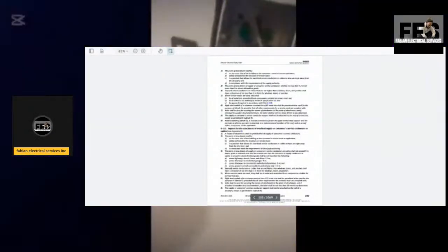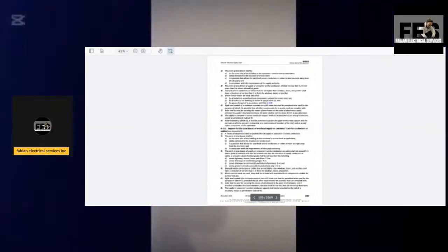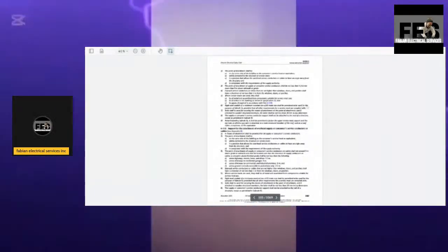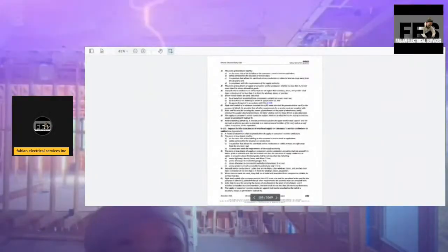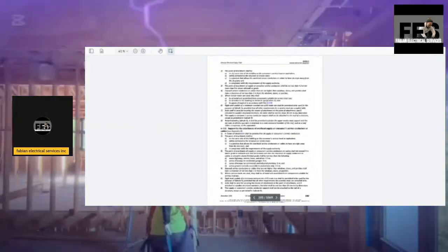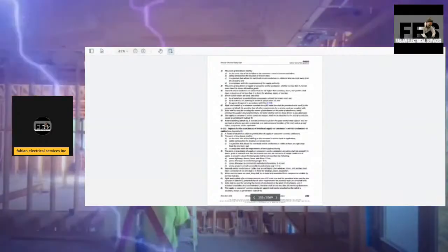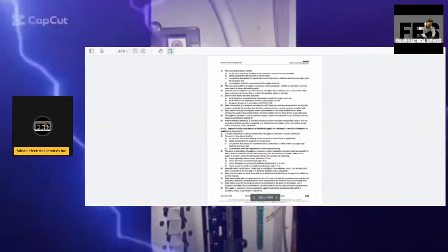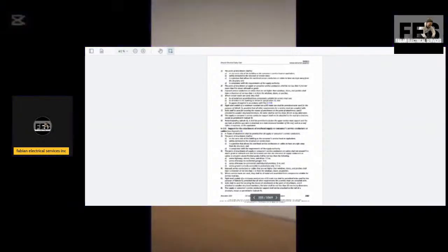Rigid steel conduit of a minimum nominal size of 63 trade size shall be permitted to be used for the purpose of Subrule 5, provided that all other requirements for a service mast are complied with. Bolts shall be used for securing the means of attachment at the point of attachment, and if attached to wooden structural members, the latter shall be not less than 38 millimeters in any dimension.